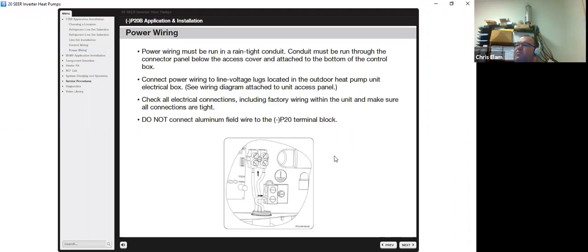Power wiring must always be run in a rain-tight conduit. Conduit must be run through the connector panel below the access cover attached to the bottom of the control box. Connect the power wiring to the line voltage lugs located at the outdoor unit. You'll see on the unit here, this is a diagram, you'll have your dedicated ground, and you'll also have a place for your L1, L2. Note, do not connect the aluminum field wire to the (-)P20 terminal block. And we'll dig into some of that as we go along too.